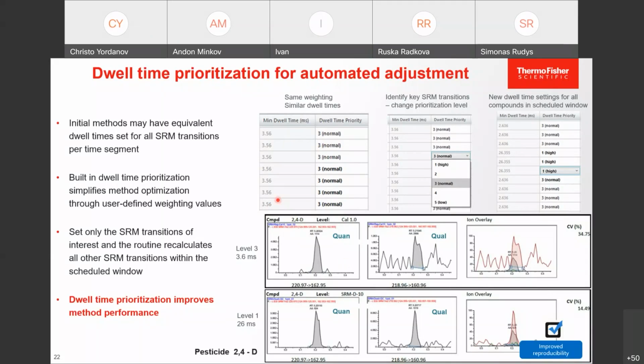But we know that some compounds perform very well, and some compounds can be very challenging. So for challenging compounds, we need to have a little bit higher, longer dwell times to acquire data, and some very good performing or good response giving compounds can be given lower dwell times. So with this dwell time prioritization tool on TSQ Plus, we can set priorities for specific compounds. For example, we took some compounds which we know from a previous run didn't perform very well. So then we took this compound and set priority from normal to high.